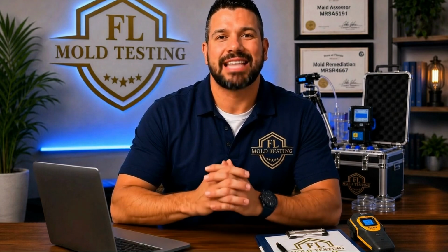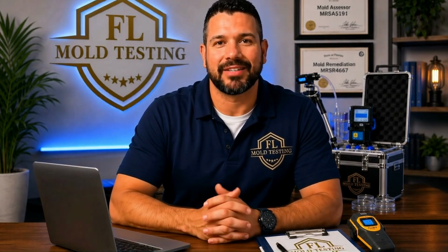To create this pressure differential, professionals use HEPA-filtered negative air machines. These machines continuously pull air from inside the containment, pass it through HEPA filters that capture at least 99.97% of particles as small as 0.3 microns, and exhaust the cleaned air outside the containment or outdoors when appropriate. Because the machine removes more air than naturally enters, the containment remains under negative pressure throughout the project. But negative pressure alone isn't enough. It works together with a properly built containment, usually constructed with 6 mil polyethylene sheeting.